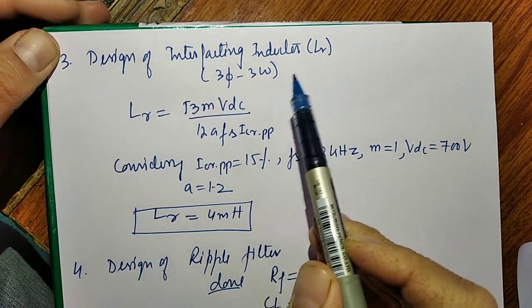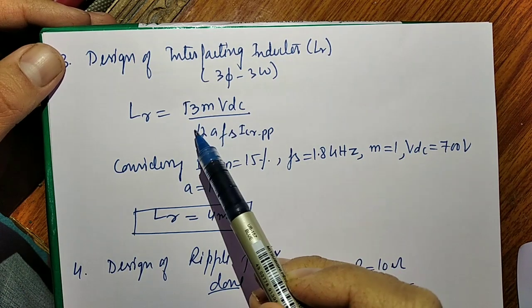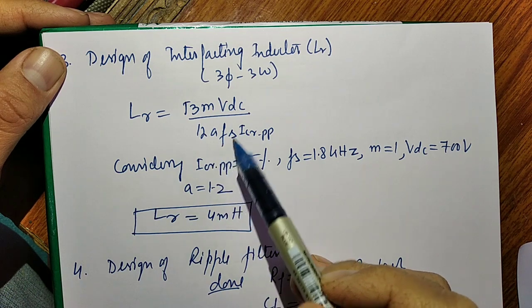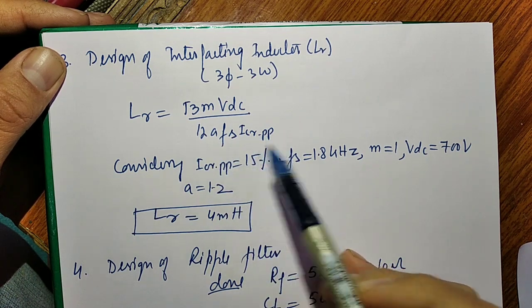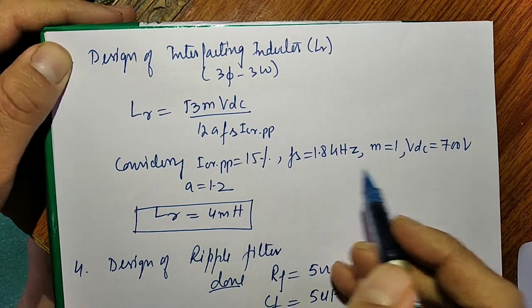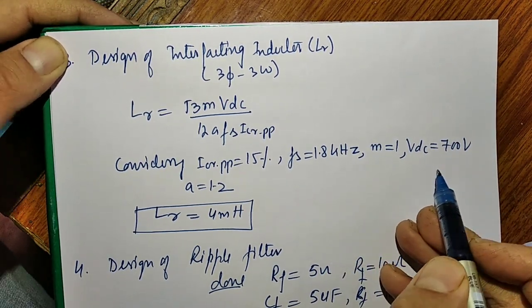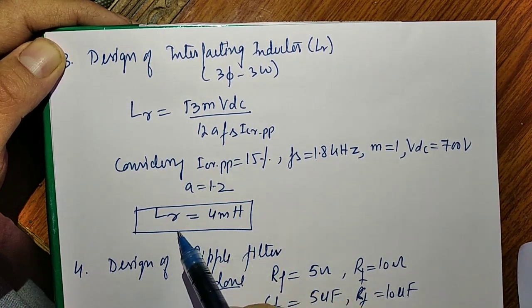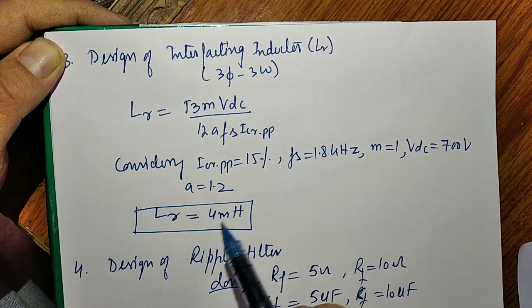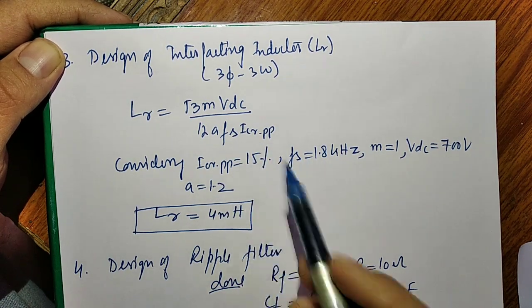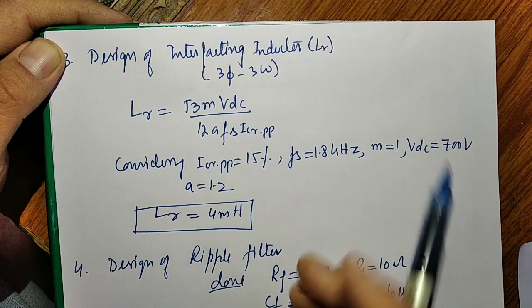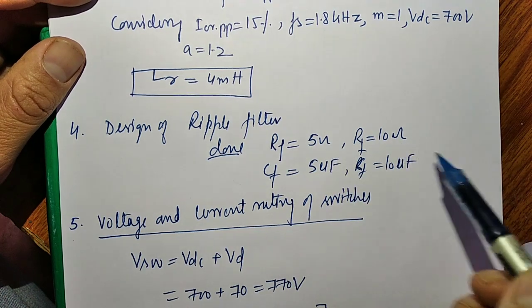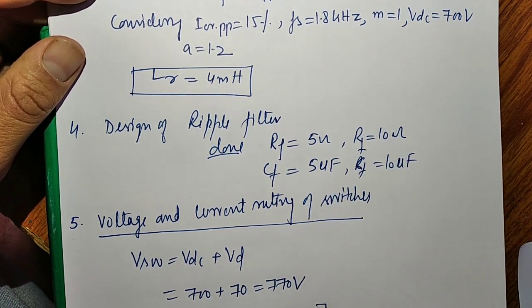For the design of the interfacing inductor in the three-phase 3-wire system, the formula is L_R = √3·M·V_DC / (12·A·F_S·I_current_ripple_percentage). With F_S = 1.8 kHz, M = 1, V_DC = 700 V, A = 1.2, and current ripple of 15%, we get L_R ≈ 4 mH. The design of the ripple filter is the same; you can take R_F = 5 Ω or 10 Ω to get different capacitor values.